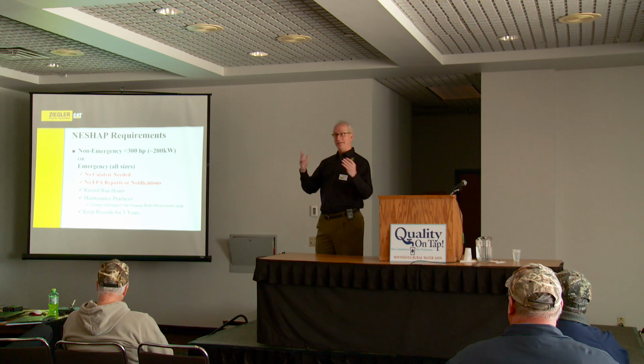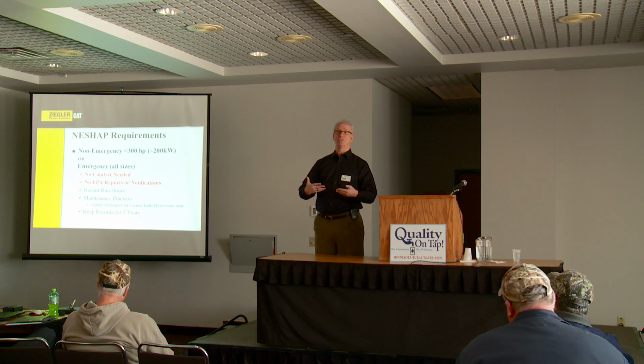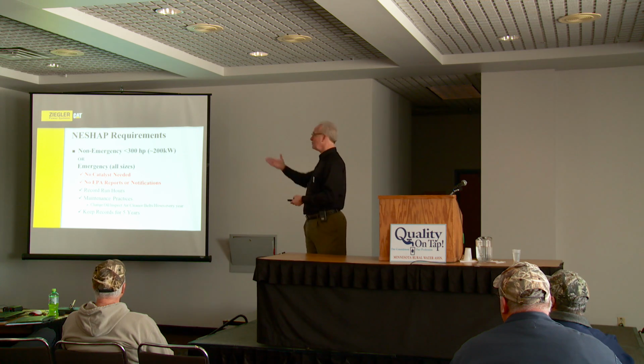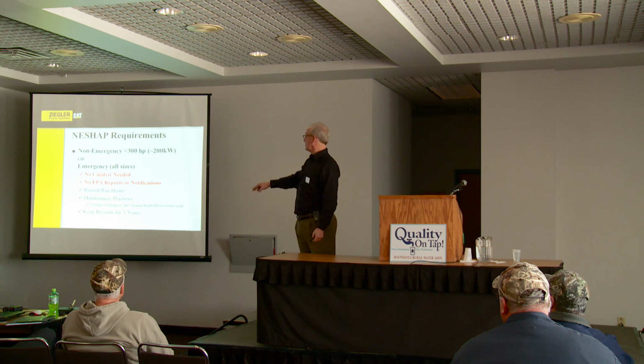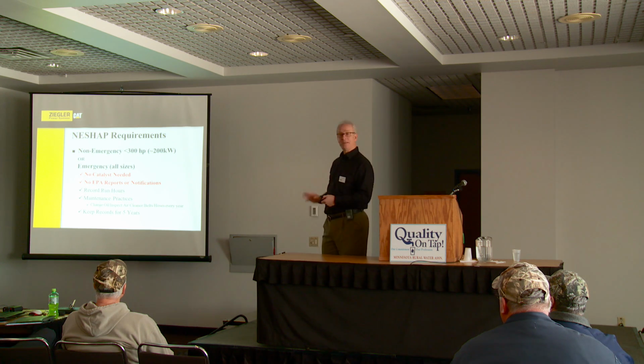So if you had all your information in front of you, you already did the date. Okay, my engine was made before June 12, 2006, so I keep listening. Now I look at my next set of information. My engine is a 250 horsepower engine. Great. Anything less than 300, and my engine is not on a utility peak shaving program and I don't run it unless the power goes out, except for testing. Then all I have to do to be compliant with NESHAP is, I don't have to install a catalyst.